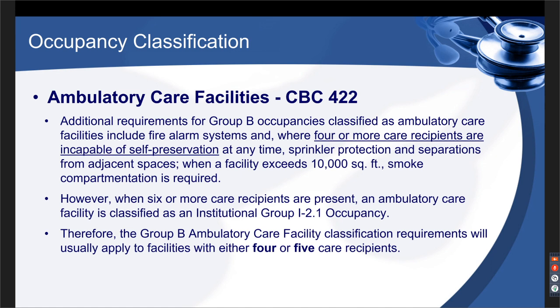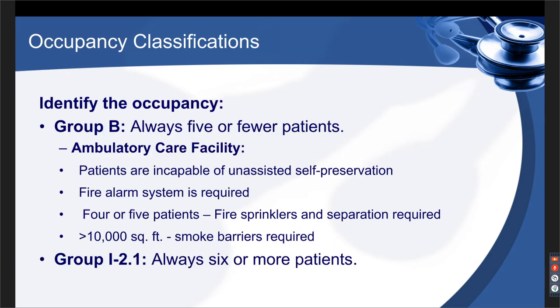And then, yes, when you have 6 or more care recipients in the ambulatory care facility, it's classified again as the I-2.1, so you go to the I-2.1 requirements. And then for a Group B ambulatory care facility classification, requirements for the sprinkler portion will apply to facilities with either 4 or 5 care recipients because of this section here that says 4 or more, where what we've read before talked about 5 or fewer. So Group B, always 5 or fewer.